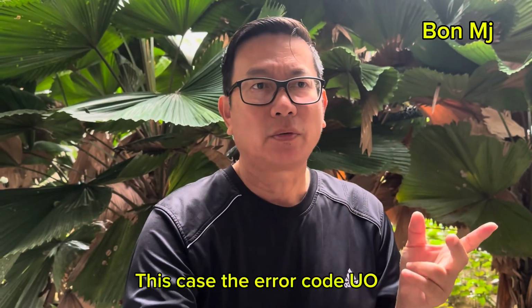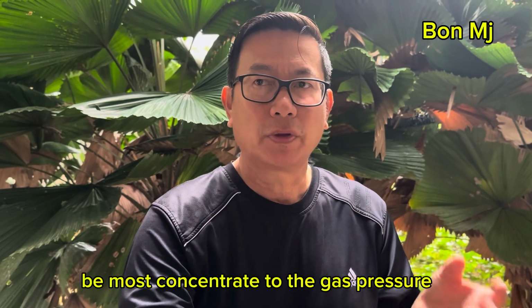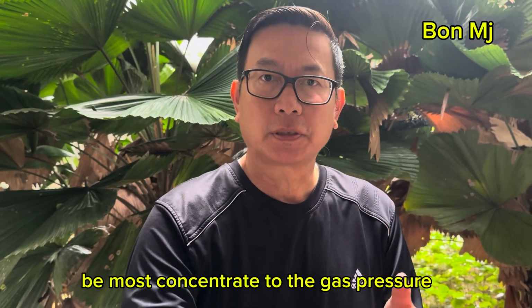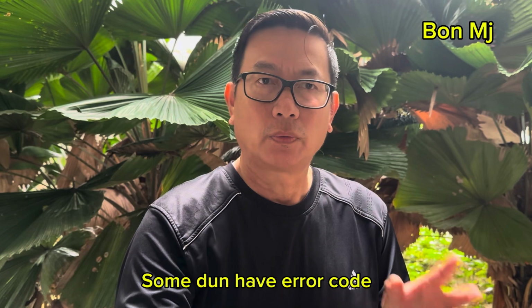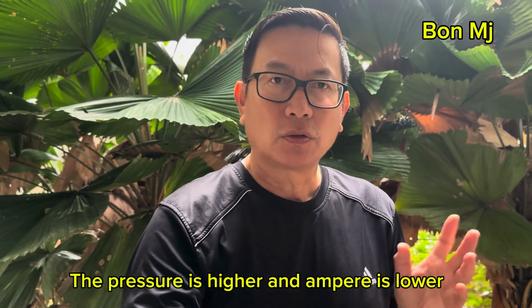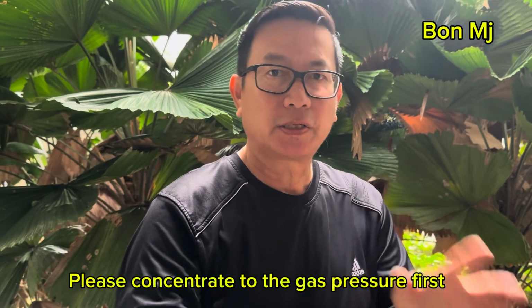In this case, actually we got the error U0, but we must concentrate on the gas pressure. Okay, some units won't have the error code, the pressure is higher and the ampere is lower. Please concentrate on the gas pressure first.